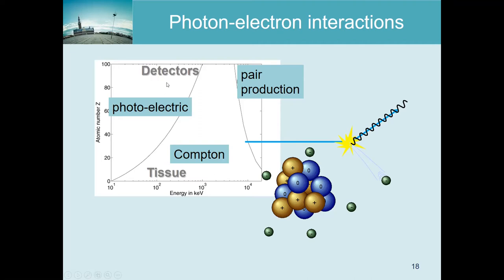In detectors we really would like to stop the photon and capture its energy, so we want very good interaction with the detector material. That is why detectors are typically very heavy - gamma cameras and PET cameras are heavy because of shielding, but also because the detector material itself must be heavy in order to work effectively.